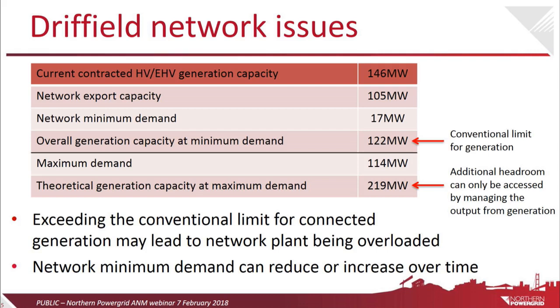So we can't connect any more generation to this network, as it could lead to the network being overloaded beyond its safe working limits. It's also worth pointing out that the demands, particularly the minimum demand on the network, can change from year to year. It's not nailed on that the same minimum demand that we had last year will occur the next year, and thereby it'll either increase or decrease the export capability of the network.